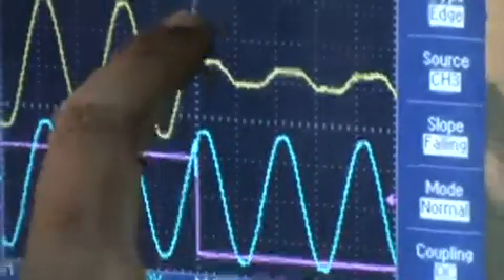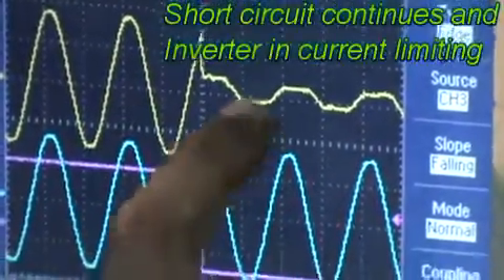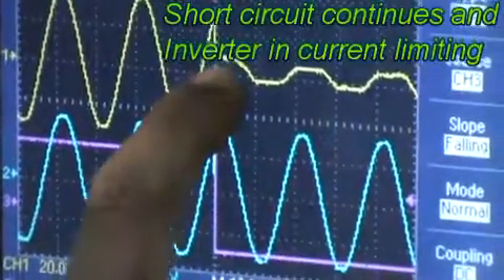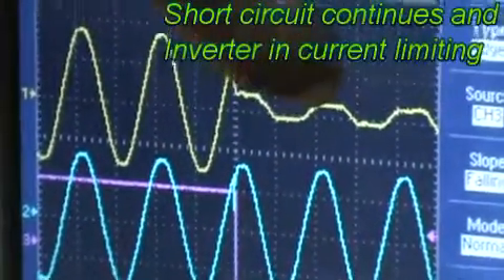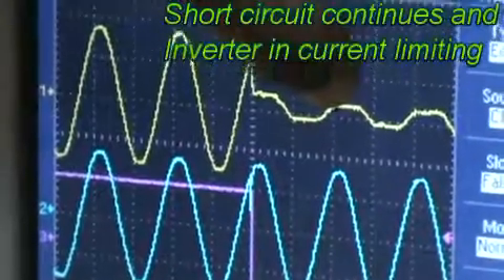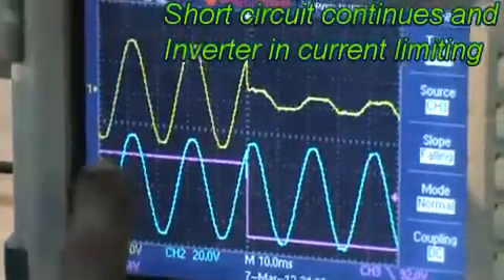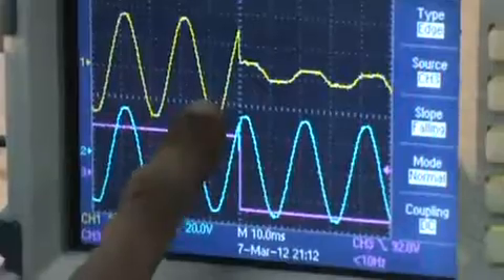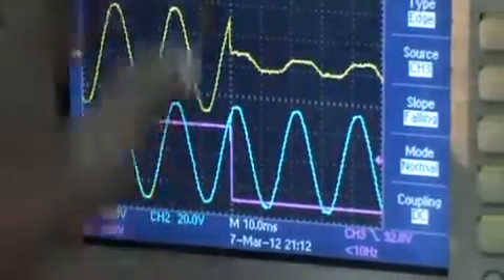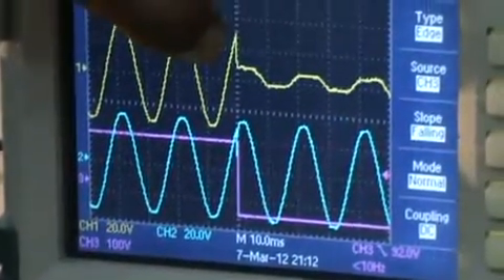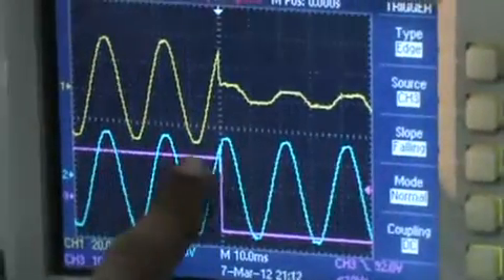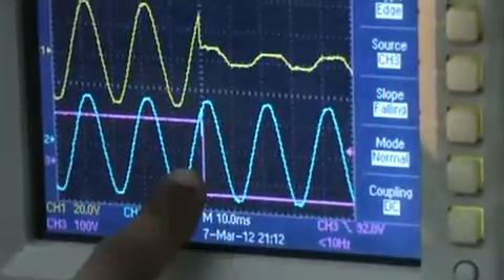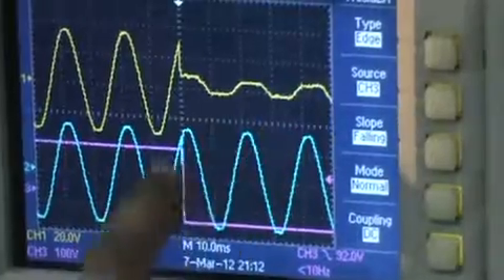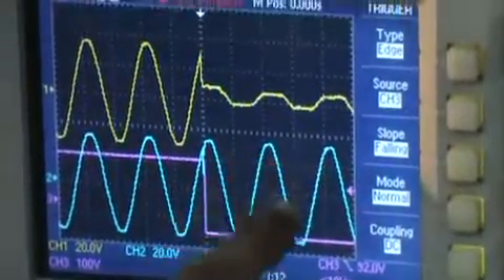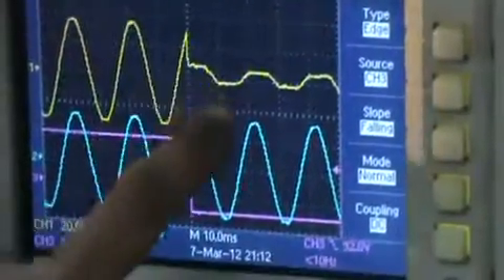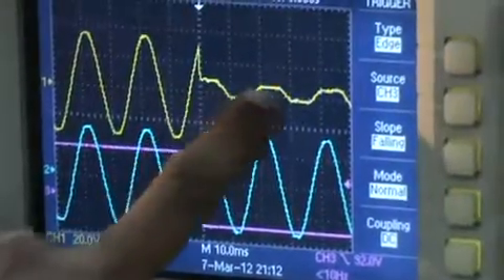Then the mains tripped immediately and the inverter soft started. See, this is the inverter soft start mode. This portion where the pink is high is the mains. This is the mains bypass. At this point the short circuit happened. Then immediately the mains changeover IGBT tripped and here the inverter soft started. At that time mains is present, but mains is disconnected from the short circuit, and here the inverter has a smooth start.